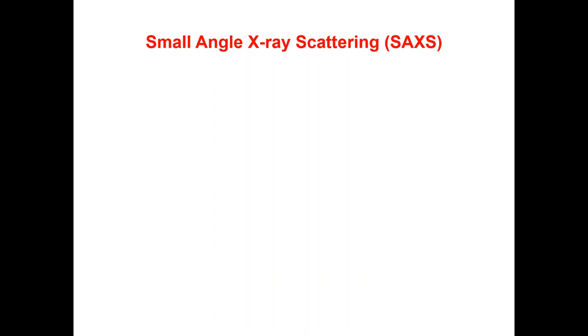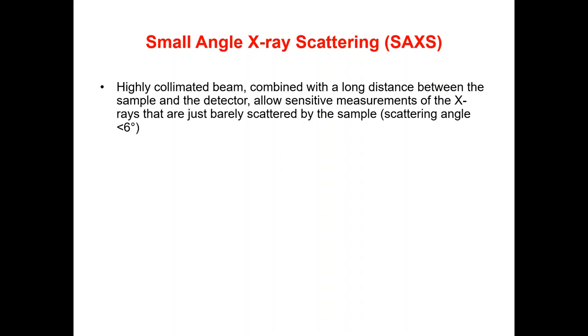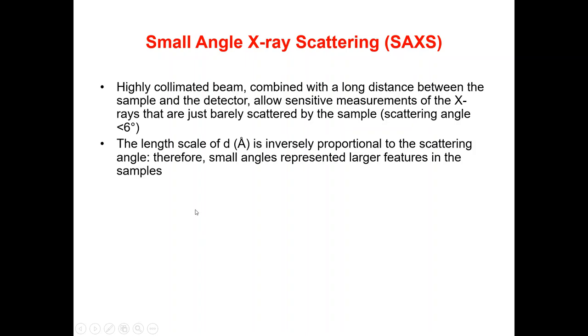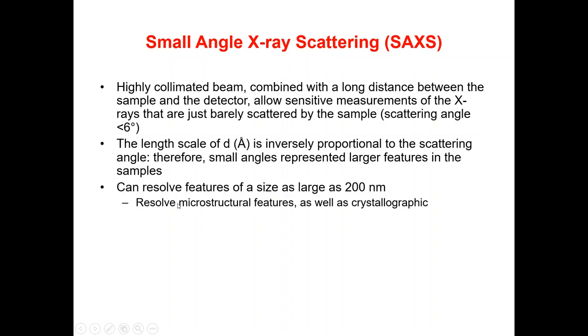Small angle X-ray scattering, called SAXS, uses a highly collimated beam combined with a long distance between the sample and the detector, which allows sensitive measurement of X-rays that are just barely scattered by the sample. In this technique, the scattering angle is smaller than six degrees. The length scale of the d-spacing measured is inversely proportional to the scattering angle, so small angles represent larger features in the sample. This technique can resolve features of sizes as large as 200 nanometers, meaning it can resolve microstructural features as well as crystallographic information.